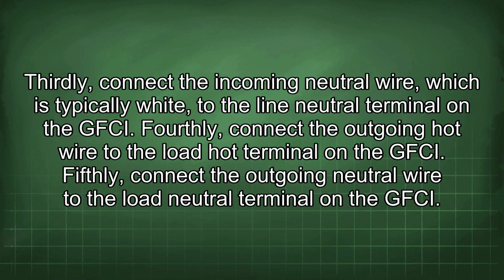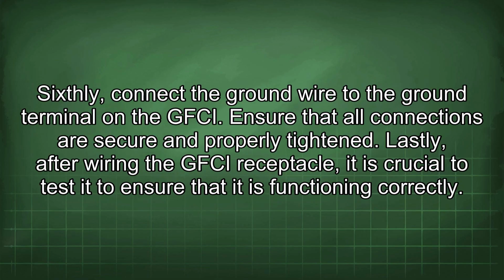Fourthly, connect the outgoing hot wire to the load hot terminal on the GFCI. Fifthly, connect the outgoing neutral wire to the load neutral terminal on the GFCI. Sixthly, connect the ground wire to the ground terminal on the GFCI. Ensure that all connections are secure and properly tightened.